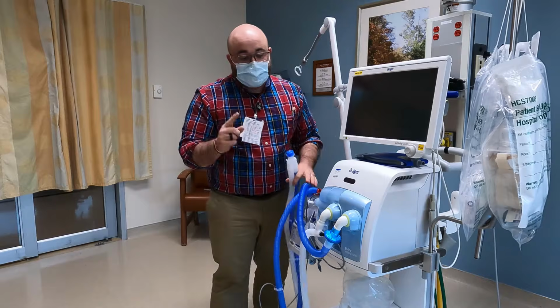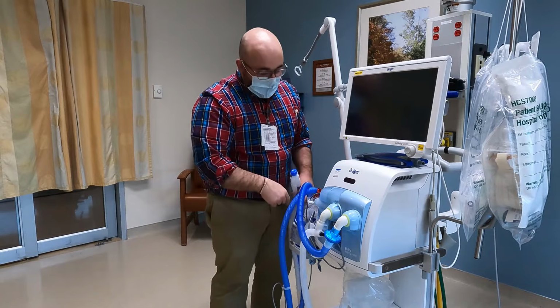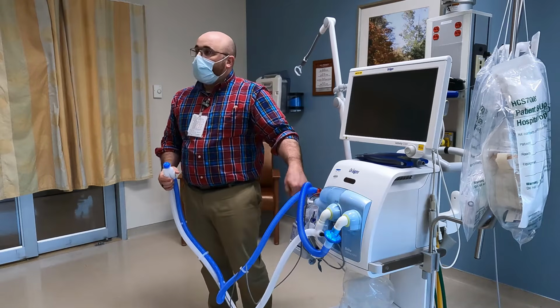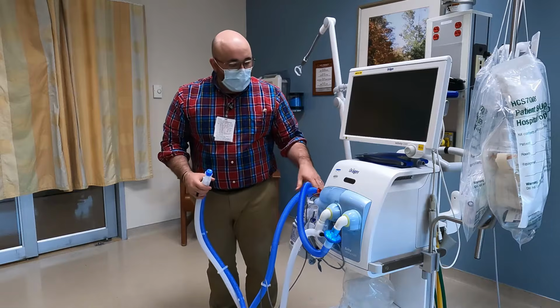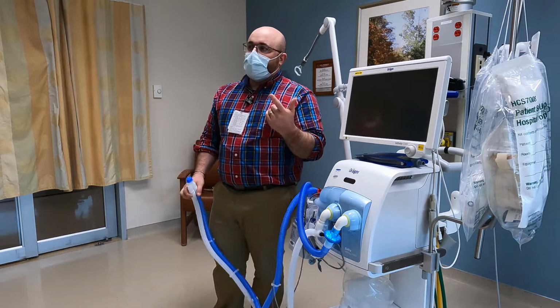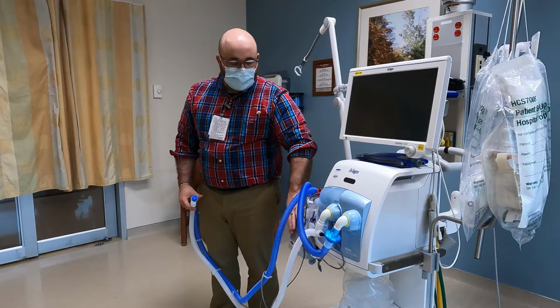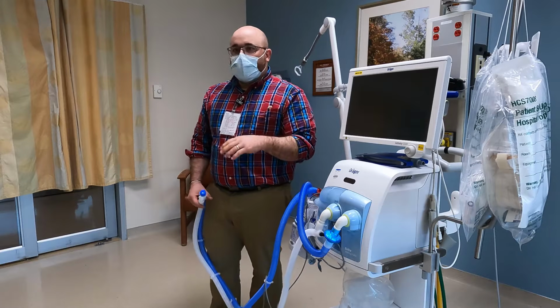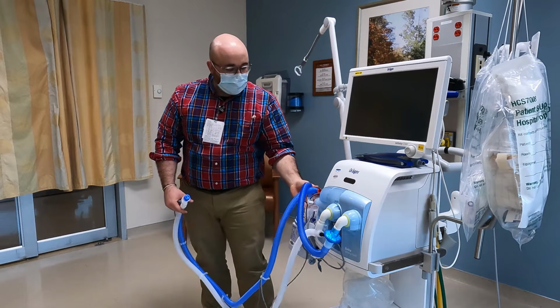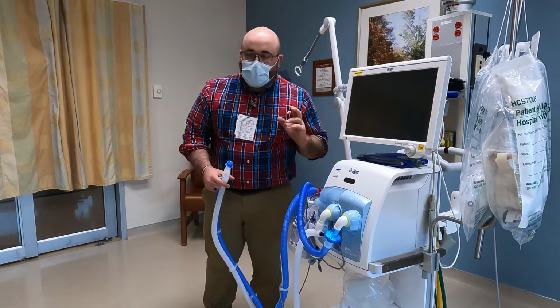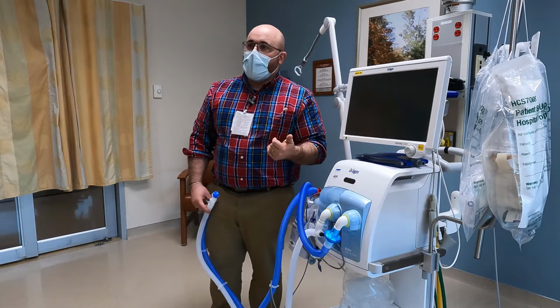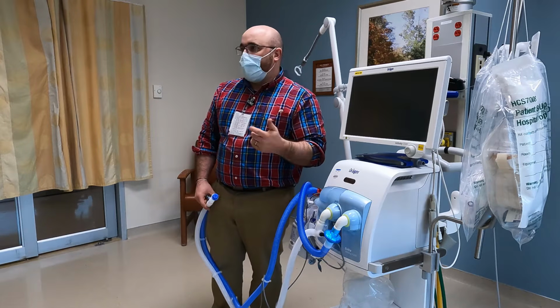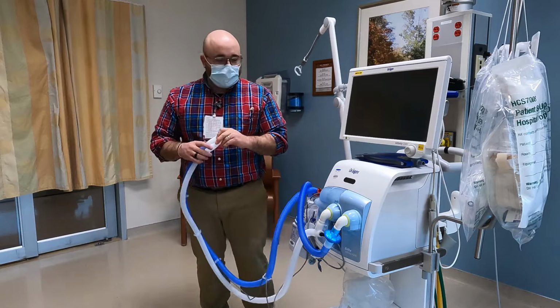Inspiratory limb, in this case, is blue. How do I know it's inspiratory? Because it goes through a heater before it gets to the patient. So we have to heat and humidify the air to 37 degrees Celsius. That's what we have it set at, and 100% saturated with water. That's why we have the water bag that flows into this chamber before we deliver it to the patient, because dry or cold air causes bronchospasm. Patients don't like it. Nobody likes it, really.